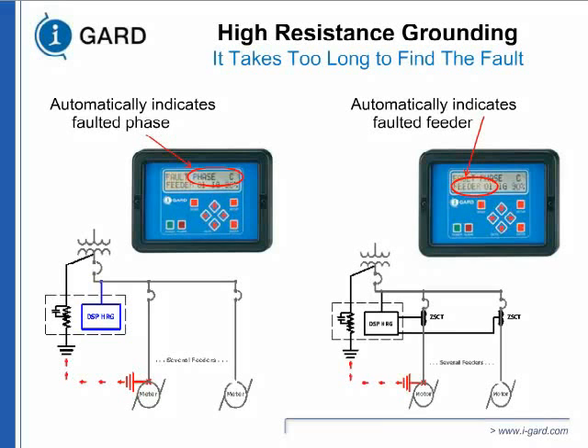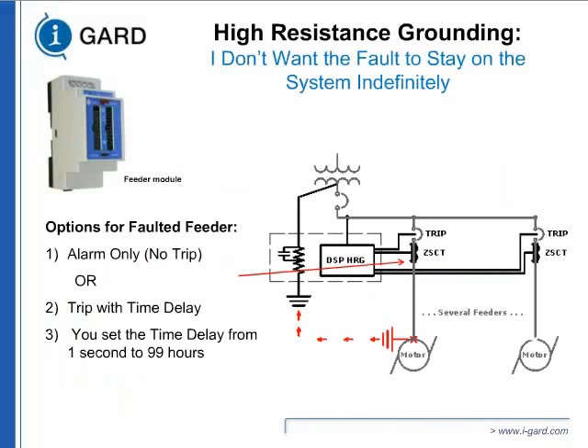Then was, I don't want the fault to stay on the system indefinitely. This is a worse way of saying I don't trust my people. They won't clear the fault. Second fault happens, then the system will come down anyway. So now you can have a timer. In some of our remote locations, we do have a timer where we give people 8 hours. By the time the alarm comes, if you don't clear it, the system will shut down, or 1 hour or 2 hours, whichever time you decide. So you have an option to customize this high resistance grounding to meet your needs.